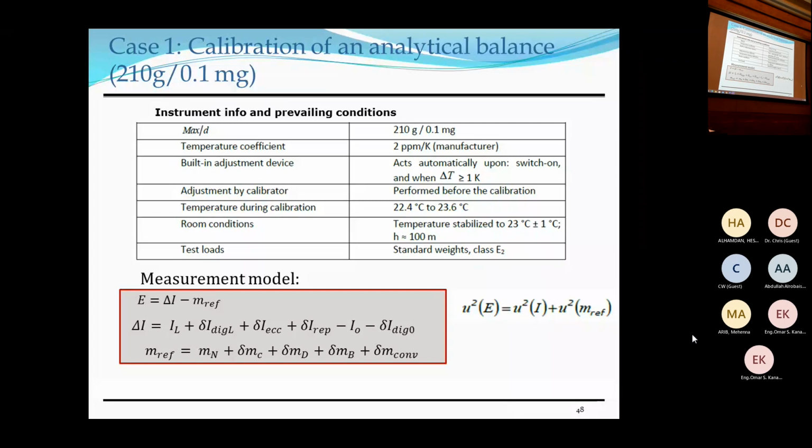So if the weight is not at the same temperature as the balance is, then there will be convectional air currents which will alter the indication of the balance. The more accurate the balance, the more prevalent this alteration.